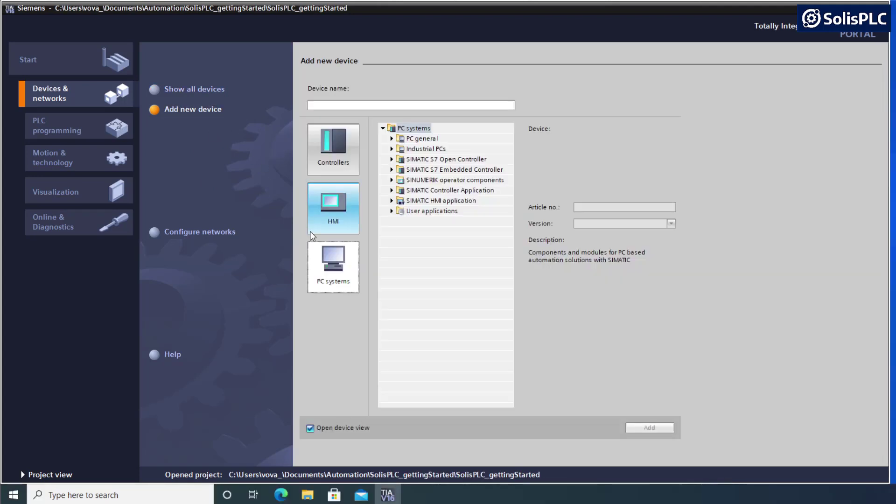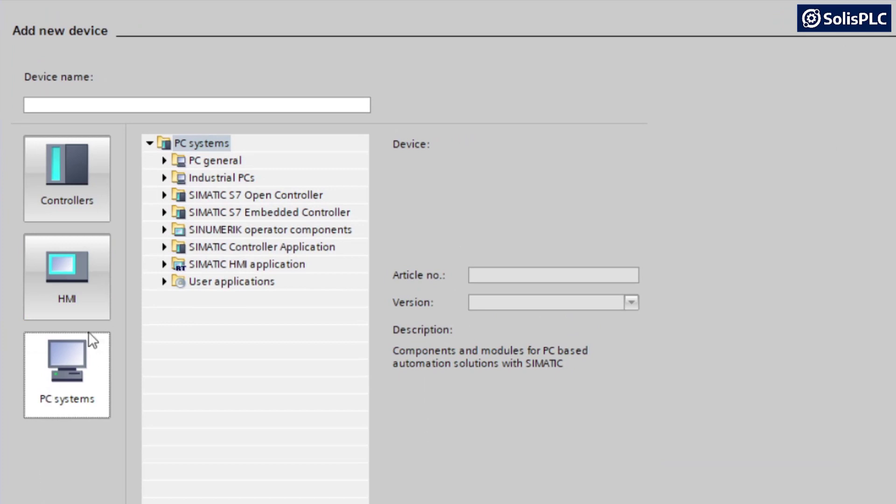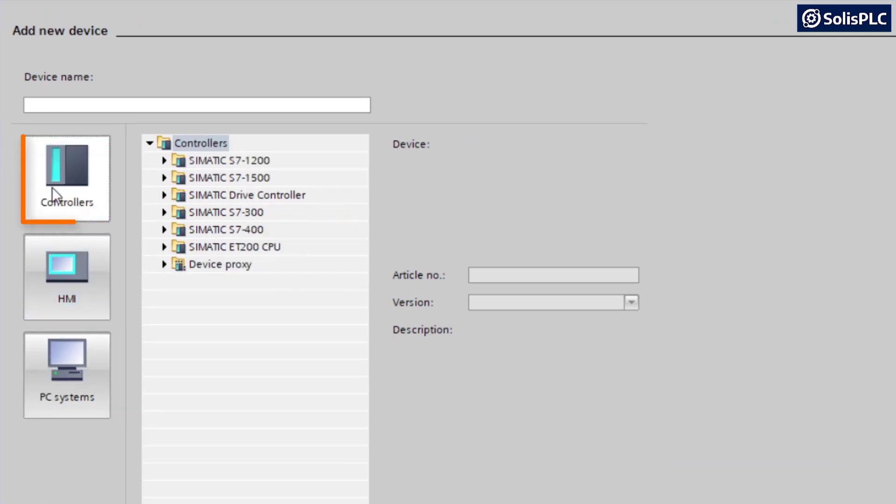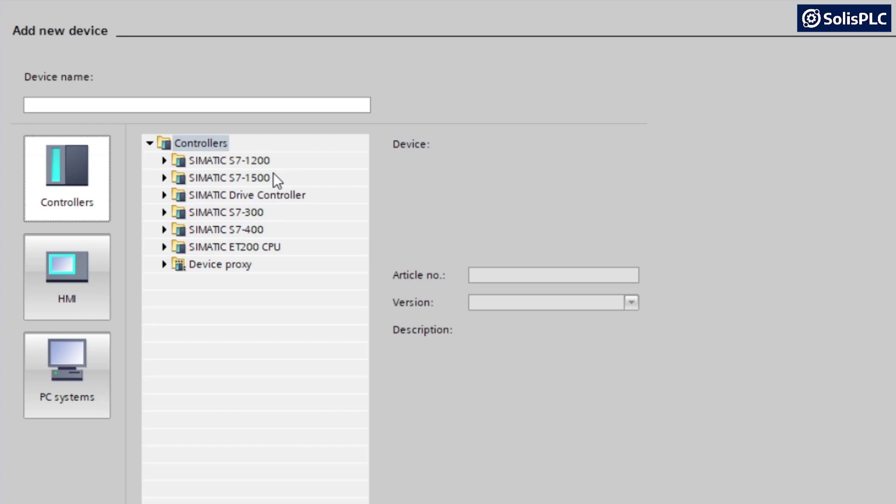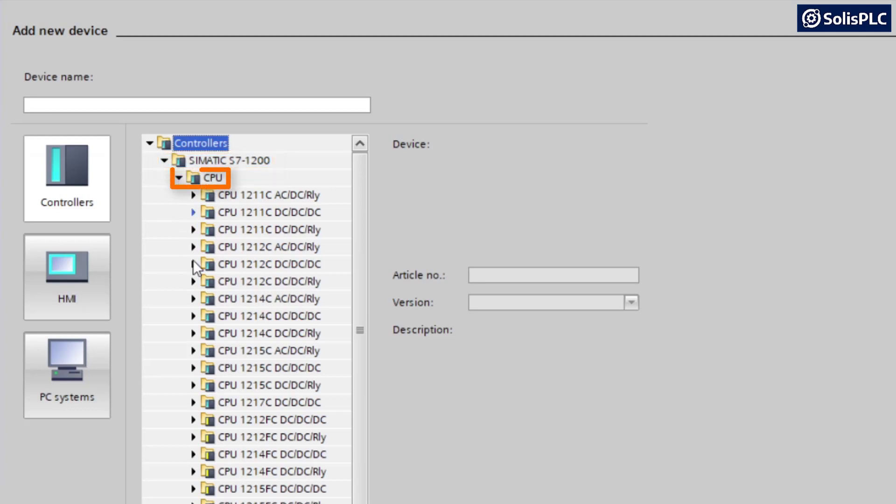At this point, we are going to need to add a PLC as well as an HMI to our project. The tabs are self-explanatory, so we're going to navigate into Controllers to select the right PLC. One thing to notice is that if you've purchased an S7-1200 starter kit, you will have access to those PLCs through the license. If you've purchased the Simatic S7-1500 starter kit, you'll have the professional license that covers the 1200, the 1500, as well as the S7-300 and 400 series. I'm going to expand the right folder and the CPU section.